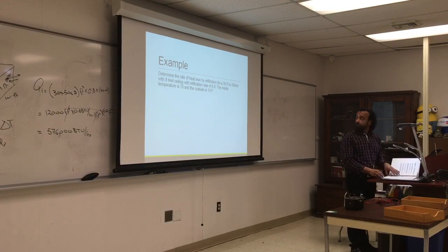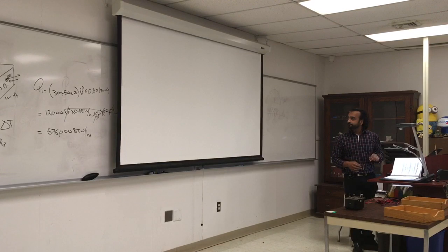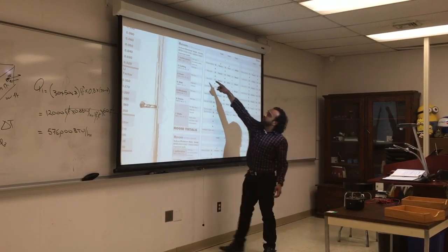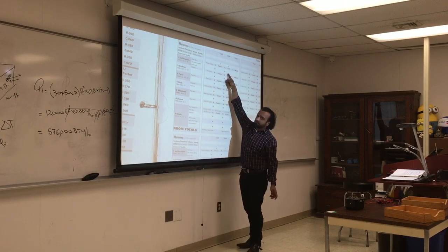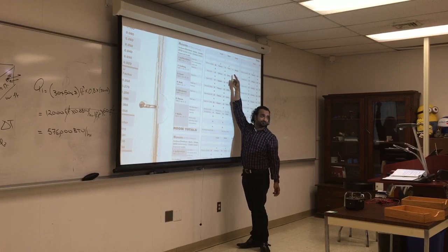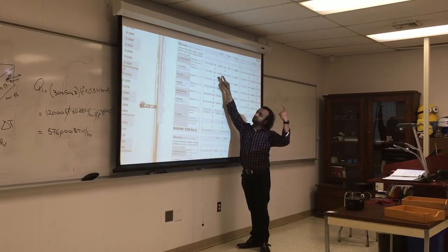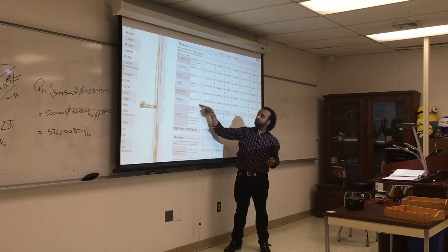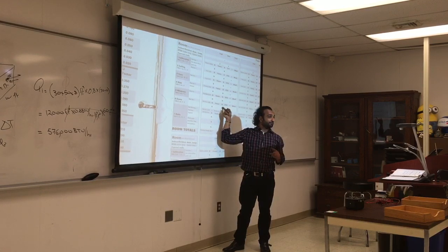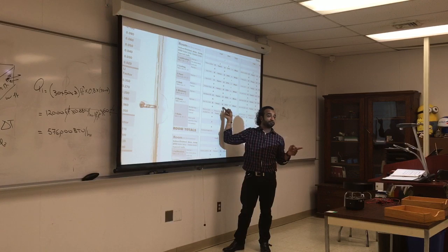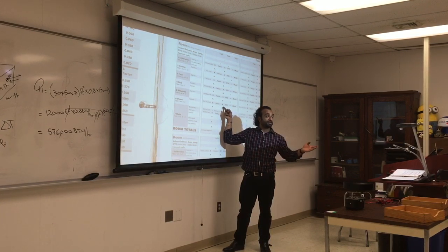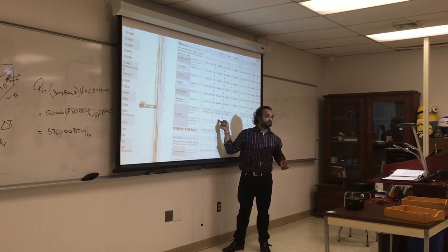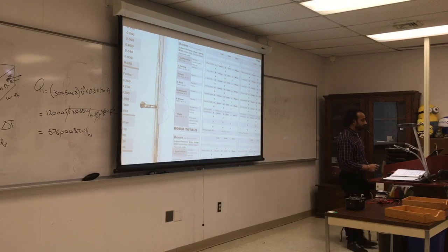Where are you going to use that? Hold on. In the project, if you look in your sheet, these cubes are for each room. Here is infiltration: volume, factor, delta T, boom, infiltration. Simple. Ceiling, transmission. Floor, transmission. Slab, if you have it; if you don't have it, just cross it out. Windows, transmission. Doors, transmission, but only if you have a door. If the door goes from the room to the inside, does it count? No. So only a door to the outside. If the room has no door to the outside, you cross it out. Then walls, which walls? Outside walls. Good?